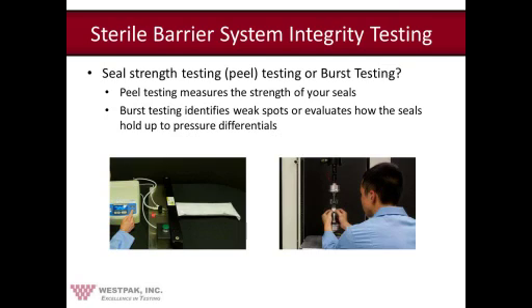And in my opinion, I would say not really. I'd say peel testing is more appropriate here because you're actually measuring the strength of your seals. You're measuring the actual force it takes to pull the seals apart, which is important for keeping your package sealed, and it gives you quantitative data on what it's like to open your package at the point of use. In a few slides, Nora is actually going to talk a little more about the detail regarding acceptance criteria for peel testing. I'll leave it at that for now.